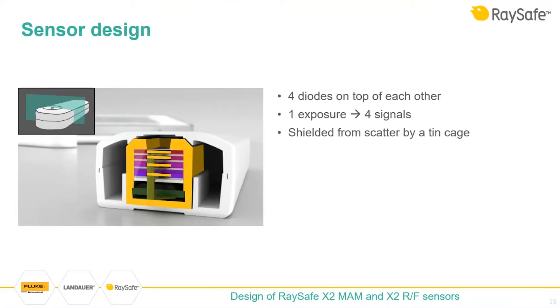The sensor is shielded from scatter by a tin cage with an opening on top. This makes it very insensitive to scatter and disturbances — we only see radiation coming from the tube. This design also makes it rotation-independent for any inhomogeneous fields, and it gives true air kerma as if placed free in air, even in a small geometry with a lot of scatter. This makes the impossible possible.